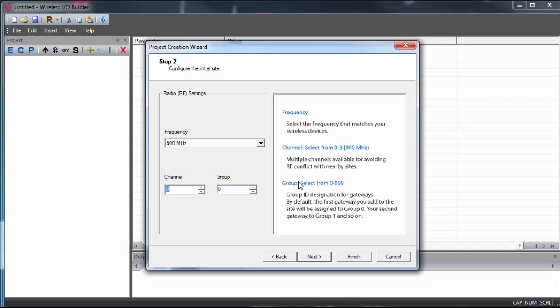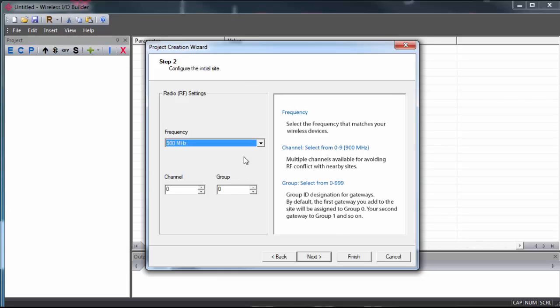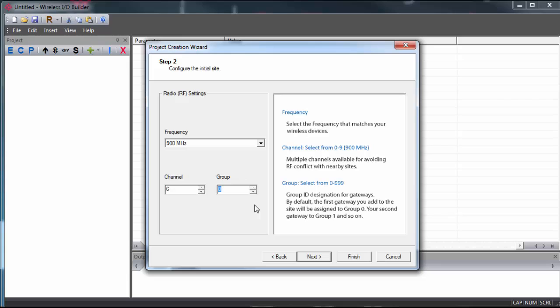Now we'll select the frequency. There are three different frequencies available. You need to be sure to pick the frequency that matches the radio in your gateway. In my case, I'll be using the 900 MHz model. By default, the channel is set to zero. It's always good practice to select a different channel, just to minimize the chances of getting too much interference on the same channel.